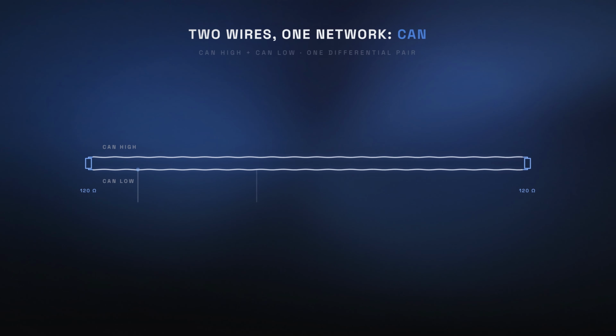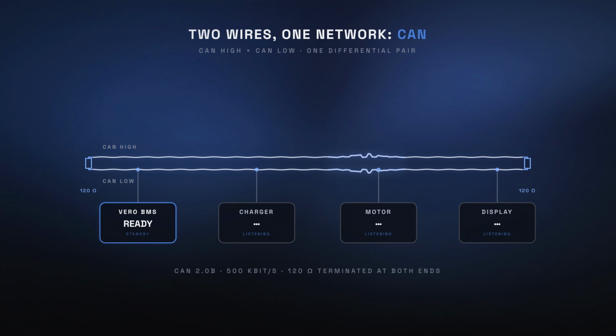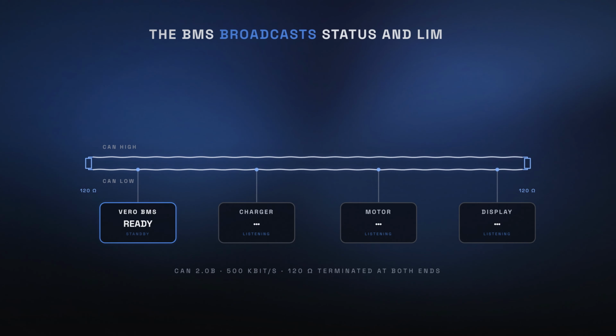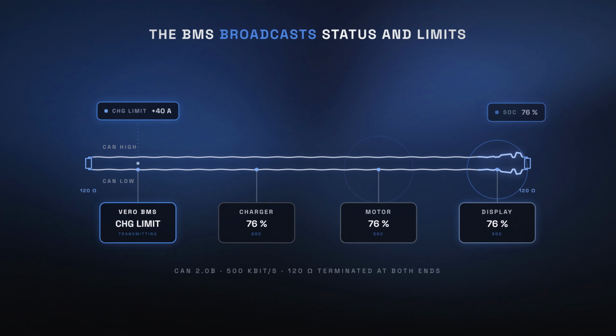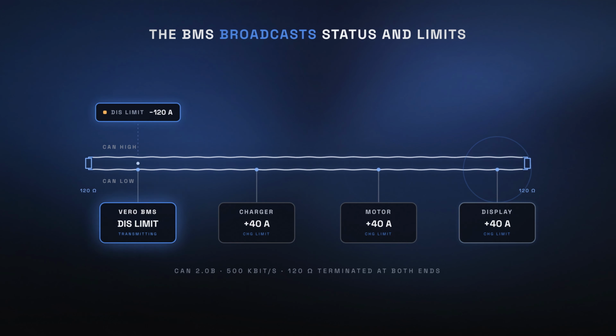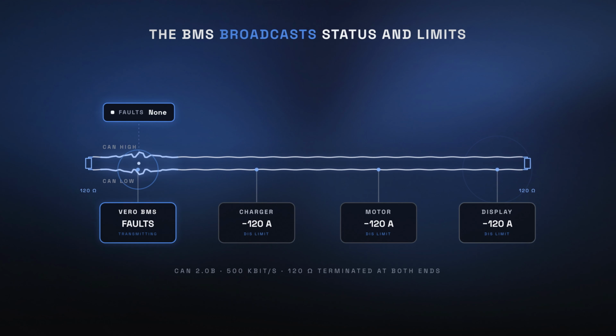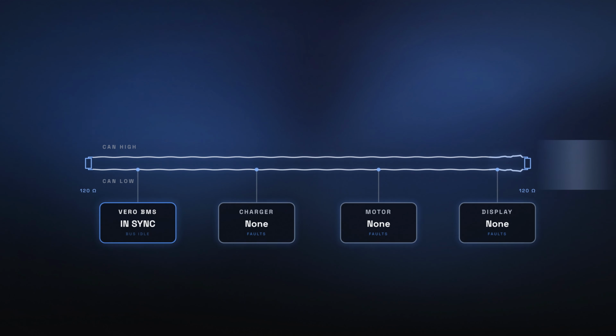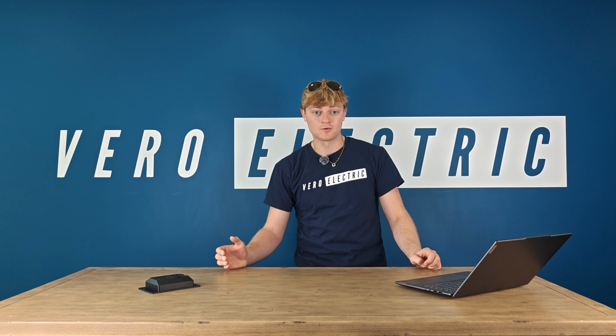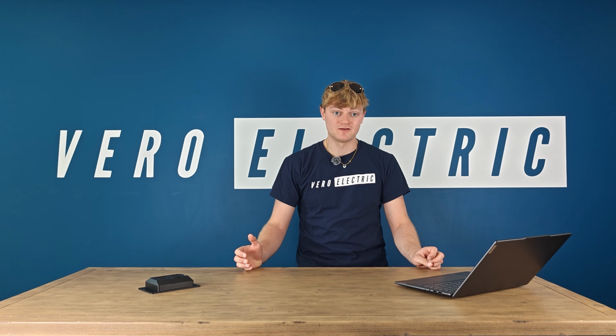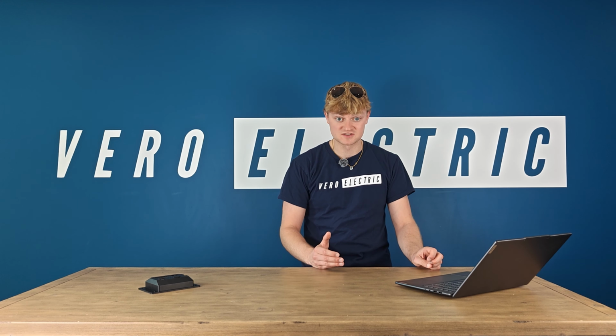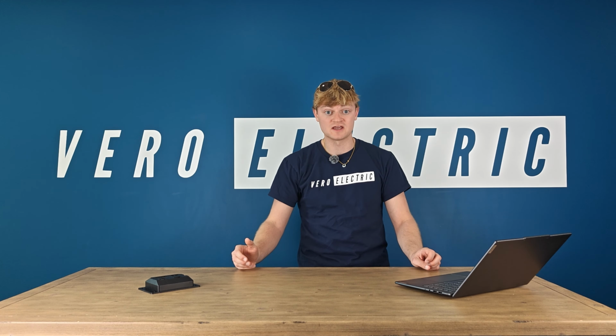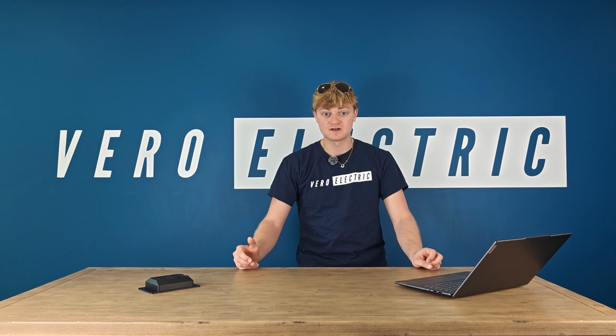Most larger systems communicate over a 2-wire electrical signaling protocol called Controller Area Network, or CAN. The BMS sends state of charge, temperatures, faults, and allowable charge and discharge limits to the rest of the system. Just as important, devices should have timeout behavior. So if valid BMS messages disappear from that CAN communication stack, the charger or inverter needs to move to a safe state.